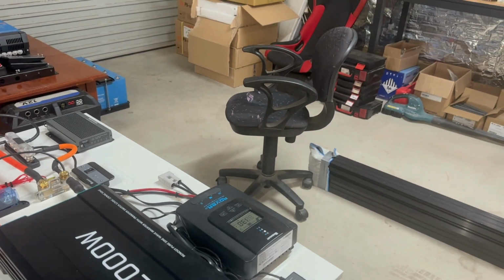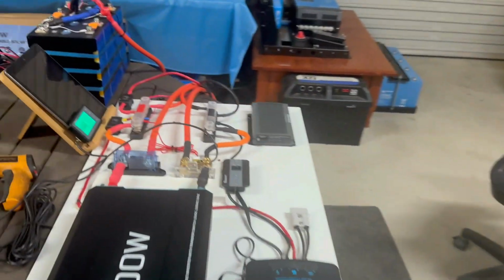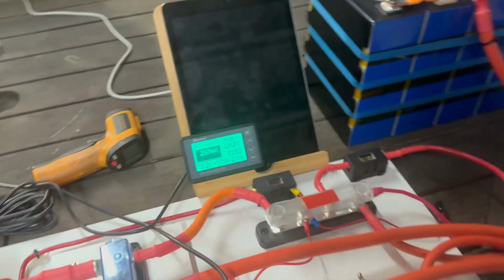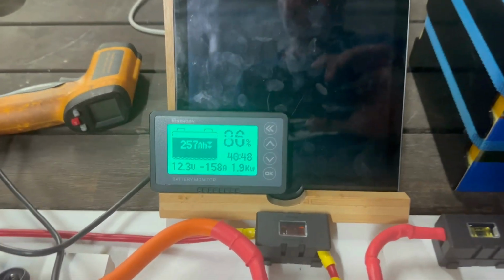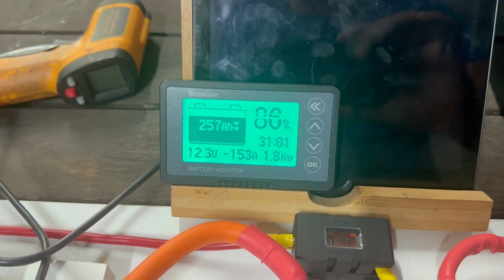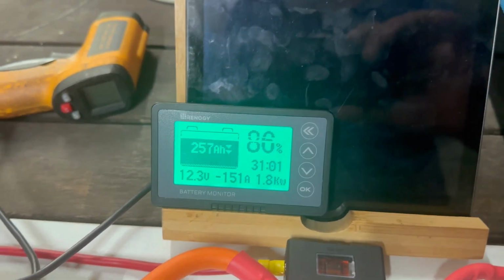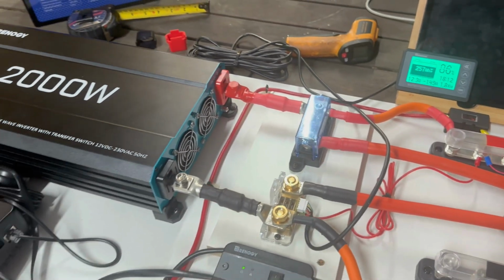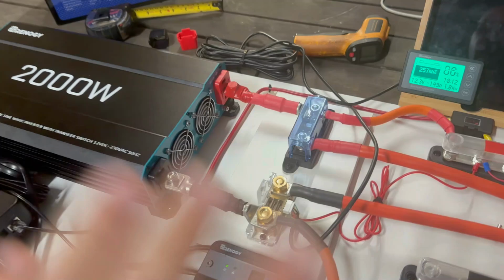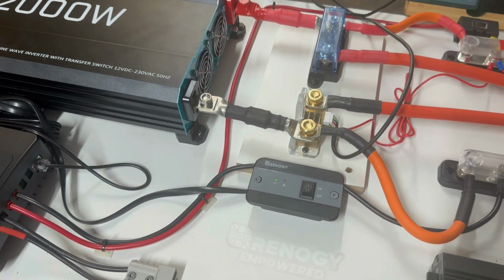That was about another 600 watts that I put on, to take it up to about 2.4 kilowatt output, and it won't run. So there's your limitation of the inverter straight away - you can see it tries to run it, but it cuts in and out.